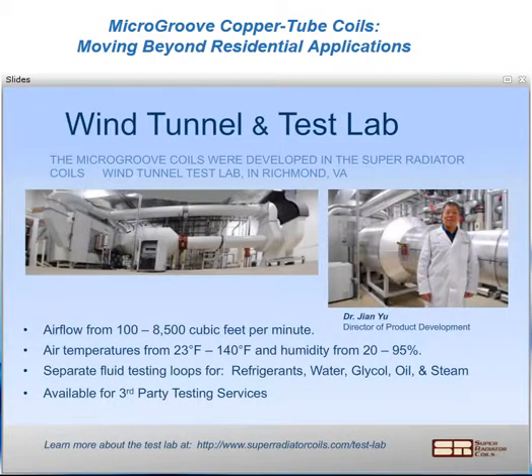The 5mm MicroGroove product was developed in our wind tunnel test lab here in Richmond, Virginia. We're very proud of this tool. You can see here listed, it has a deep bench of capabilities, a wide range of airflows that we can operate the test lab under. We can introduce humidity rates. We can run several different fluids through the coils that are tested in the lab. And in development of the 5mm tube product, we use water to get the primary heat transfer coefficients, and we're able to run refrigerants to then validate those in condensing and evaporator conditions.